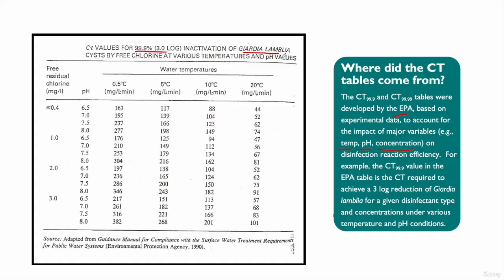In other words, if chlorine is able to remove Giardia lamblia, it will also be able to remove viruses and bacteria. This is why I am designing for the worst type, the hardest pathogen to be removed by chlorine, which is Giardia lamblia. And a kind reminder: for Cryptosporidium, if I am facing high levels, better to use UV. Otherwise, we need huge levels of chlorine, and this will not be feasible.